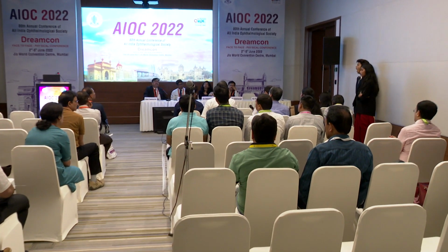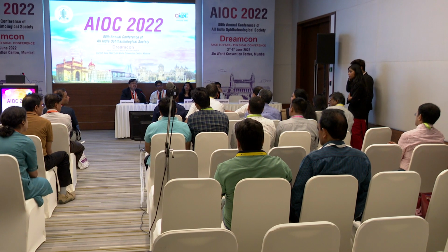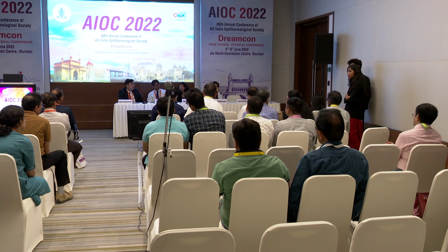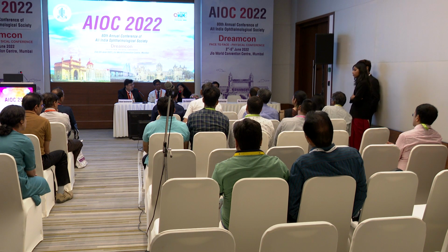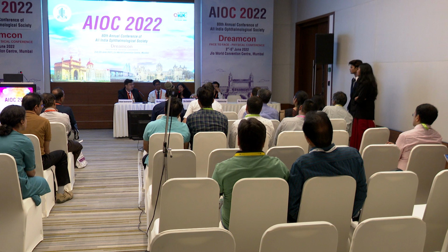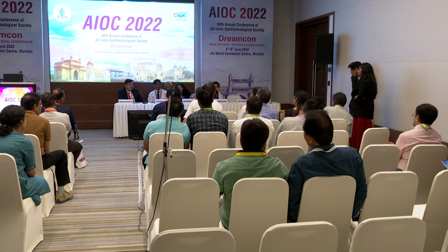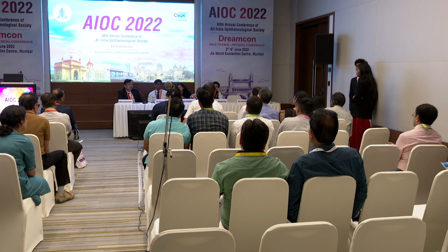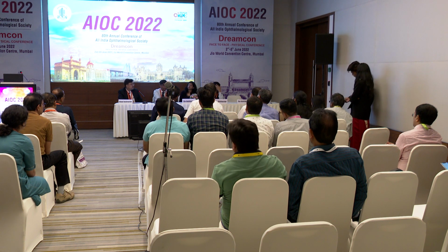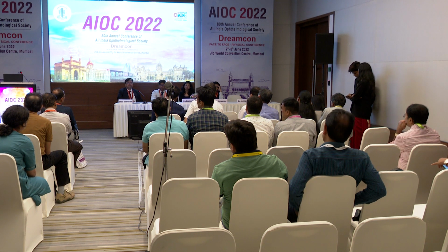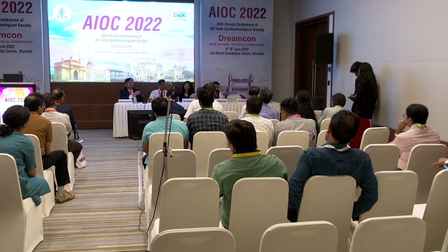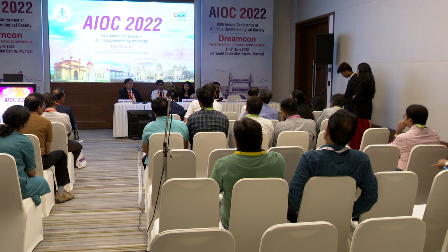Must there be two entries for the operation theatre, or is one entry sufficient for NABH? Ideally, the operation theatre should have one entry. Two entries, one for the patient and one for the doctor, is for the OR complex, to come to the induction area, but the operation theatre as such should have only one entry. But the other thing we have to take care of is that the instruments coming in and going out should be different. The soiled instrument should go out through a different window panel, and the fresh instrument through a different one.